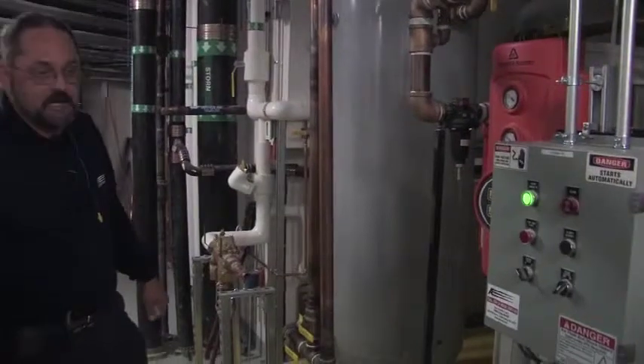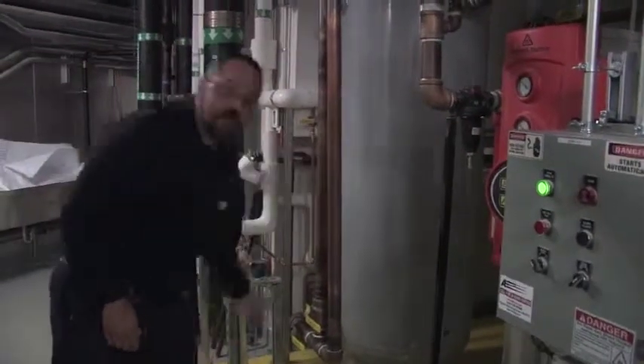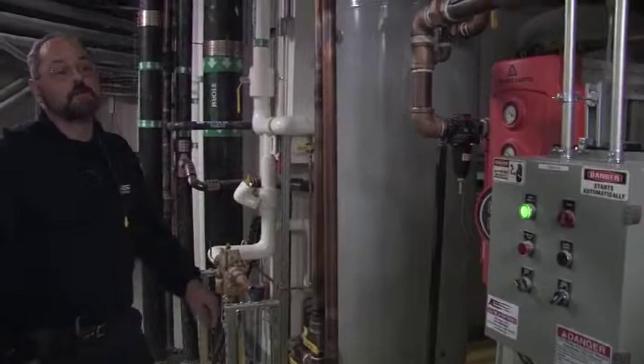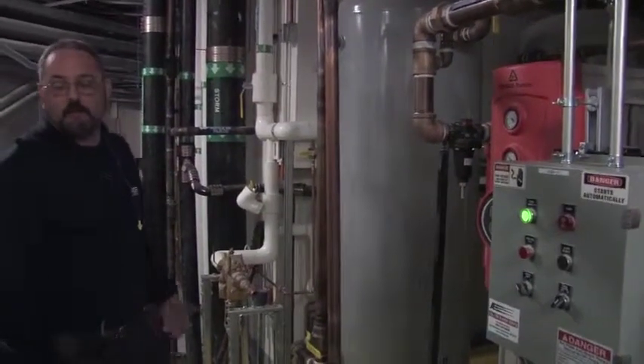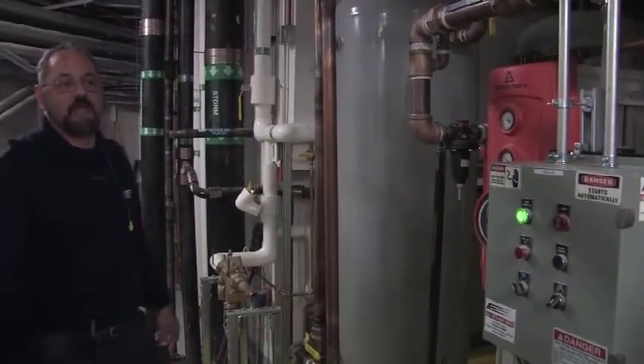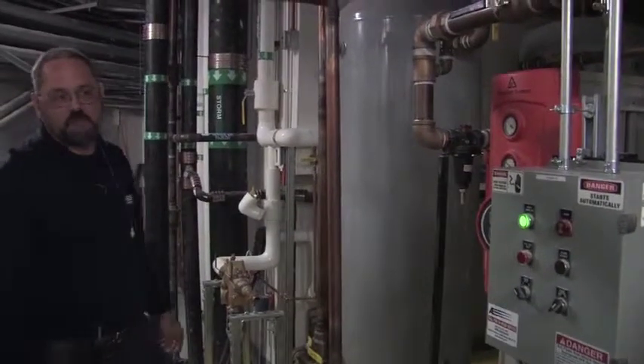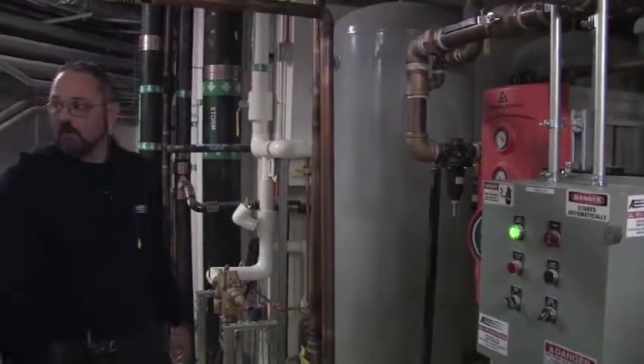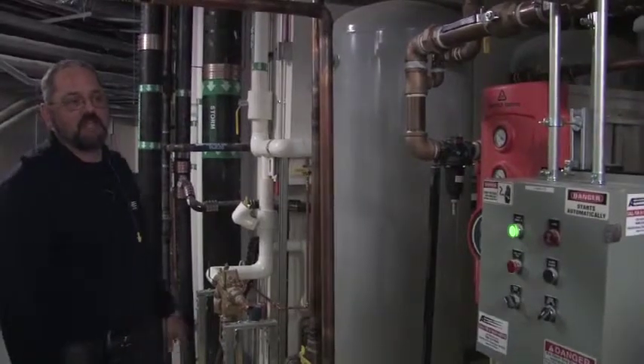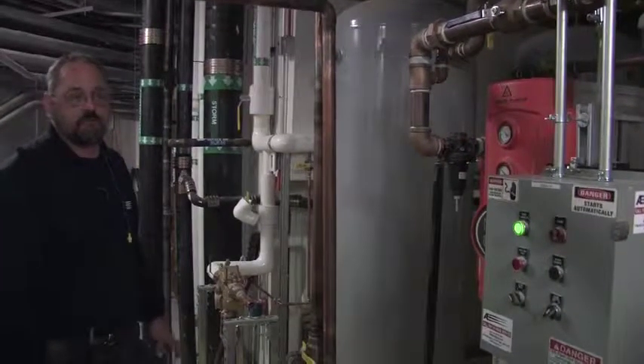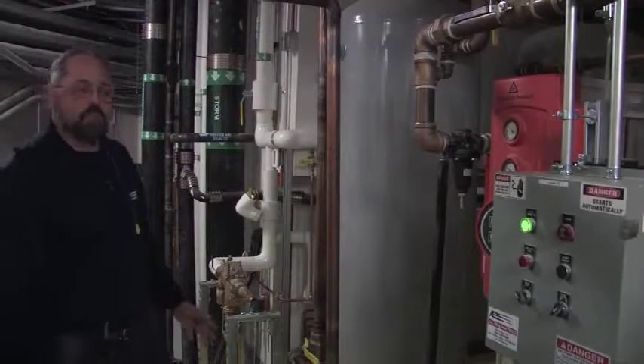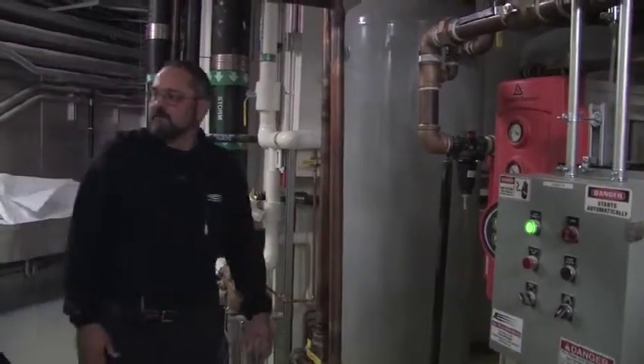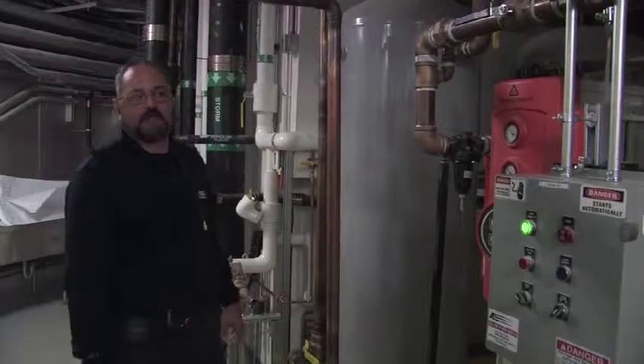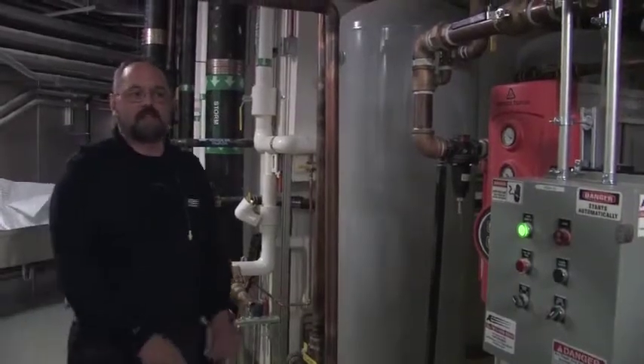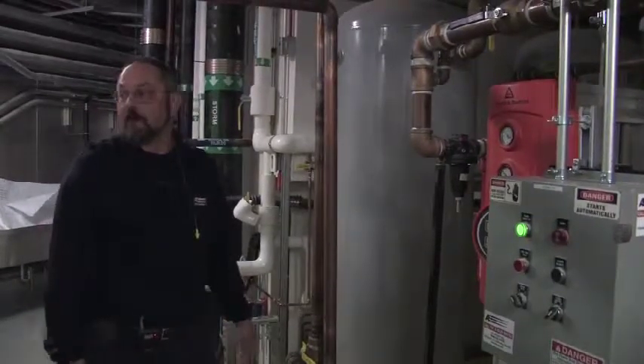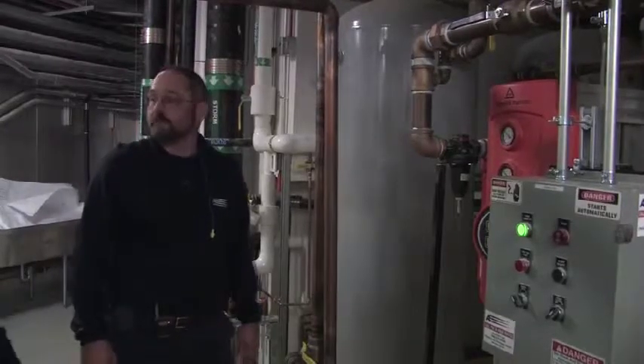They did say they were checking the other one. They were pushing the test button on the drain and firing it off. Oh, there's water flowing out. Yeah, not all of it. But I looked at it, and they had it set to open 2 seconds every 25 minutes. So I'm figuring they were probably off by about 10 gallons a day because the new tank had been in for about 3 months. If it was full of 2,000, you know, about 2,400 gallons, it was accumulating at 8 to 10 gallons a day. And it was a hot, muggy summer, so it made a lot of water.